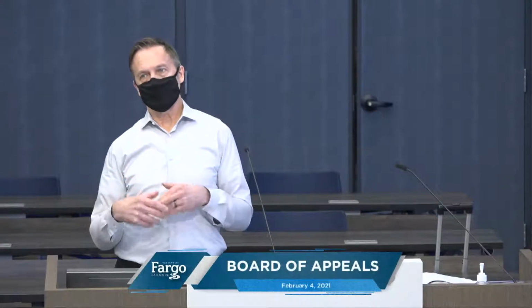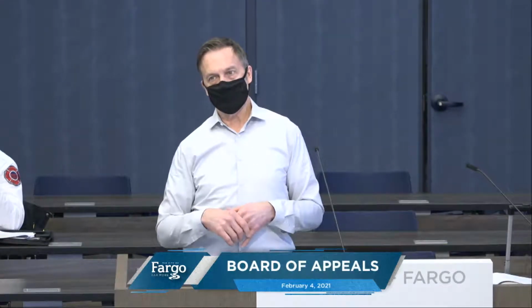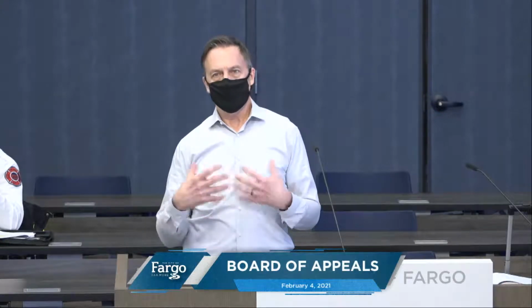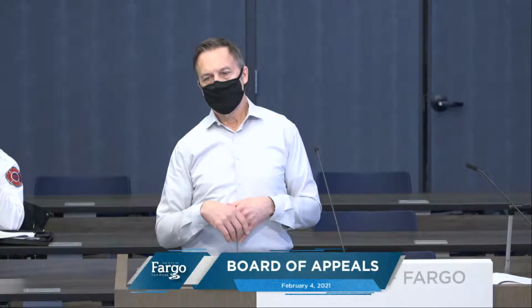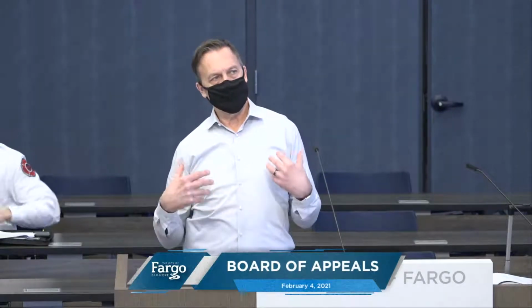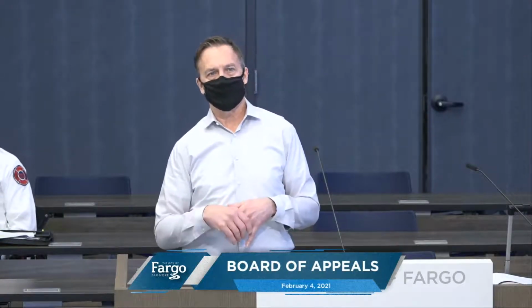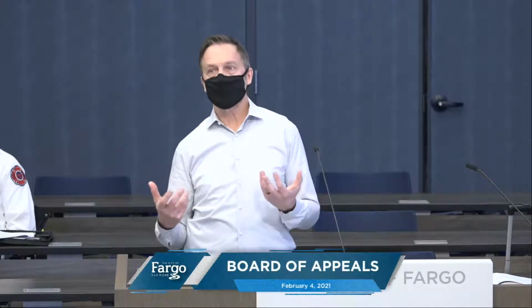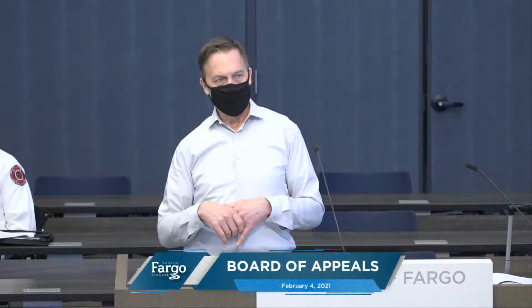There are other parking garages that are open in this town that have dedicated spots. You're going to let them separate them and have nothing? Sure. I look at it like it's a private garage in that strip apartment building. 1,000 square feet. The code's telling us we don't want anything to burn but that 1,000 square feet if something should happen in that space. It's the same here. That's how we're thinking. The 1,000 square feet needs separation.